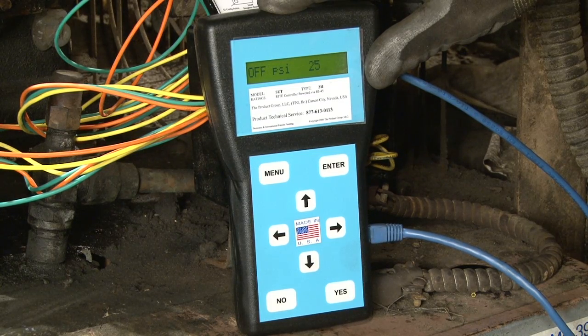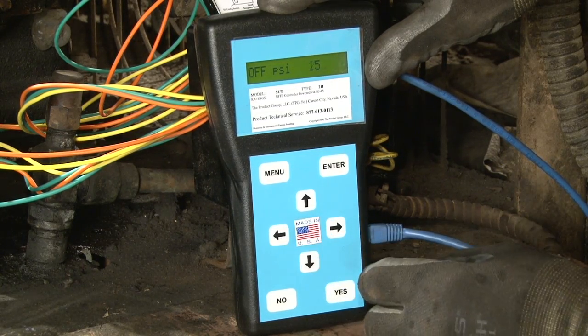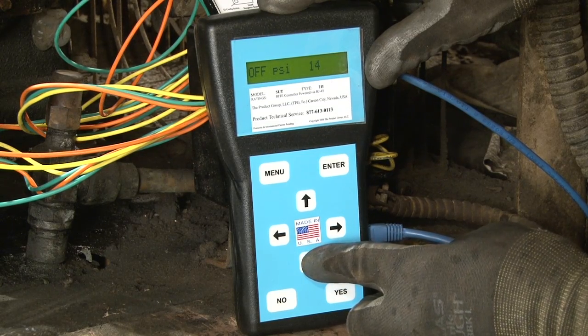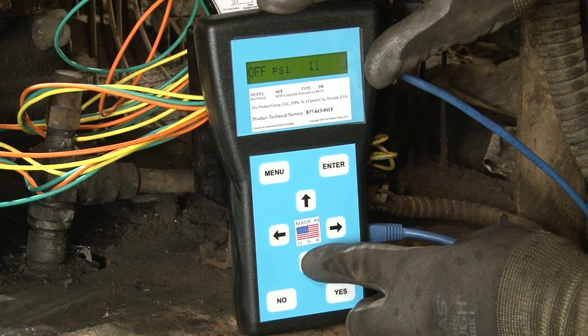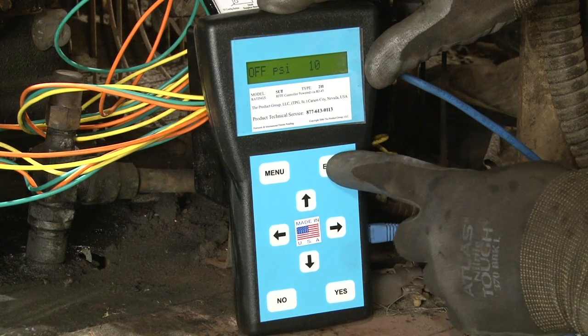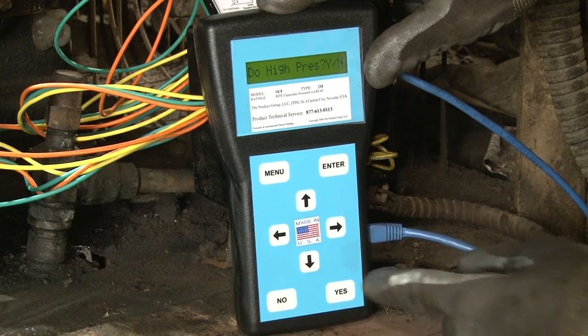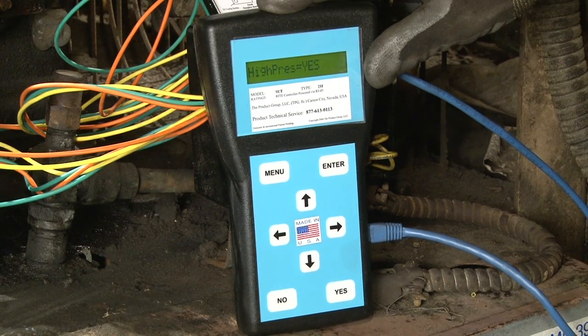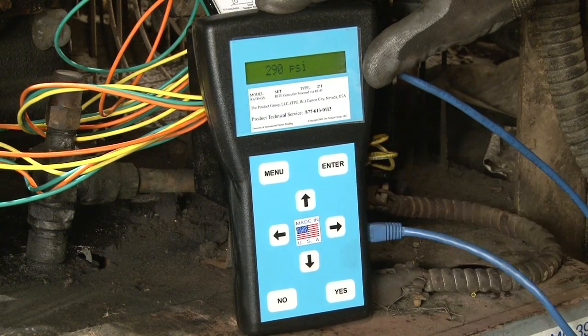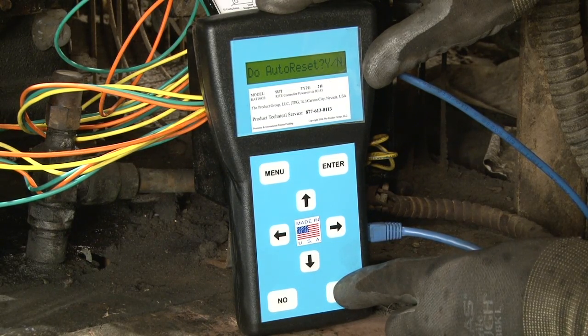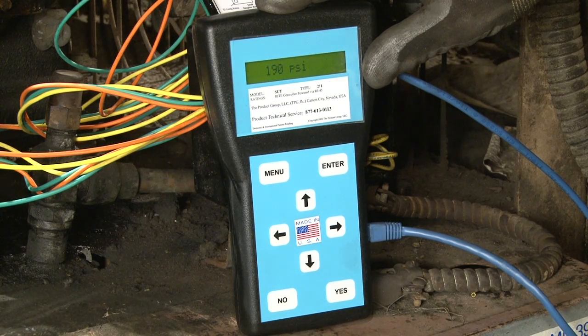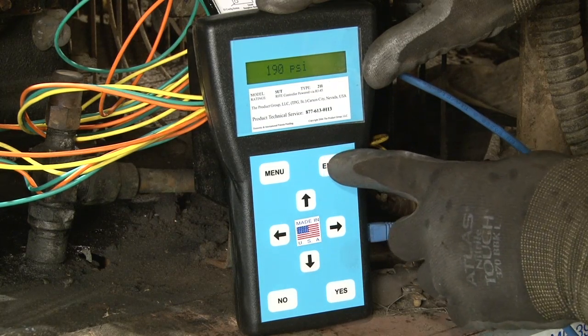Next, it asks us for the off pressure set point. We're going to move from the default set point of 25, as shown by using the arrow keys, to the set point of 10 psi, and when we're there we press the enter button. Next, do we want to do high pressure? The answer is yes. The default is 300. We want 290 pounds. We press enter. It asks us if we want to do automatic or manual reset, and we choose to do automatic reset. The automatic reset limit is 190 pounds, and we accept that.